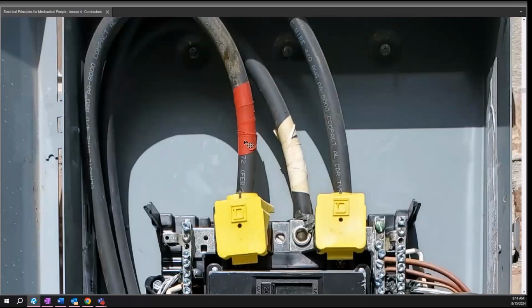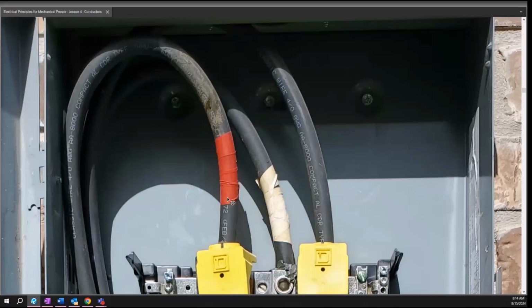If somebody only took one round turn on this and it wasn't blatantly obvious that this is meant to be the red conductor, the AHJ can say, hey, you need to identify this better. That means come put several round turns on it so it's clear this is a phase conductor, the red phase conductor. Every now and then they'll require that because the tape can dry out and start falling off, and by the time ten years goes by, it may fall off completely, leaving you with two blacks and no way to know which is which.